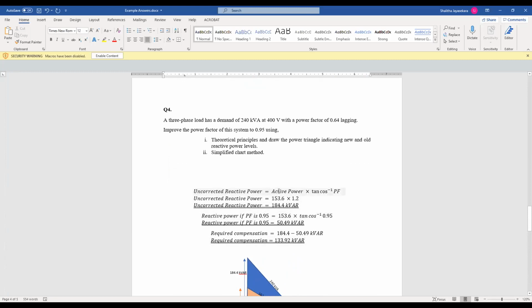In here I think I have directly taken the active power. If you have the apparent power and the power factor, you can easily multiply this value by this value, and you will get the active power value. I will write this down here. Active power will be equal to apparent power into power factor. So this will give you 153.6 kW. This is the active power component in this system, so that is the value we used here.